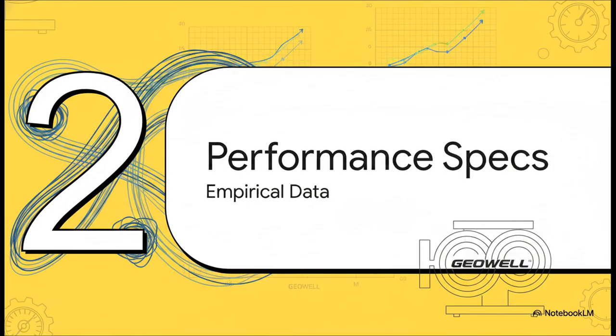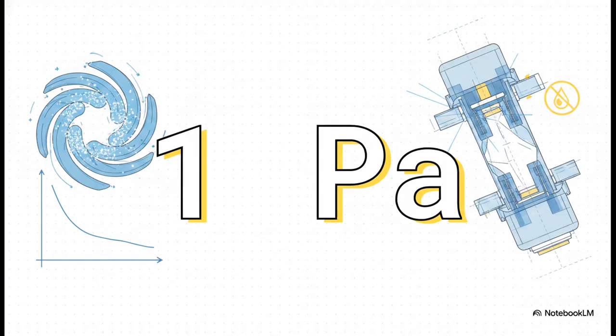Let's look at the empirical data and actual capabilities. When we talk about sealing and compression, the numbers really speak for themselves. The larger models in the lineup, specifically the 600, 800, and 1000, can hit a phenomenal ultimate pressure down to exactly 1 Pascal. To put that into perspective, that's about 7.5 times 10 to the negative 3 torr.